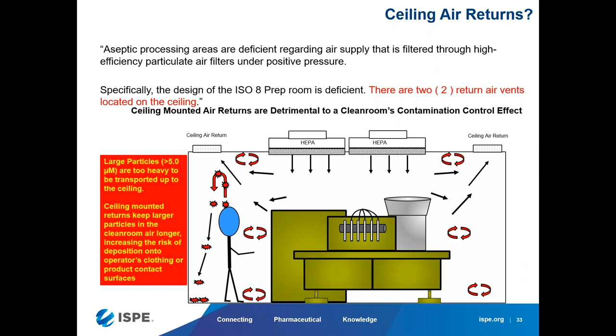Great example is a facility that my team audited. Luckily the client caught it and said, we think there's something off here. They wanted a sterile sampling booth in an ISO 8 room. But the ISO 8 room had ceiling returns, and the sterile sampling booth had negative pressure. That means anything from outside can go inside the sterile sampling booth. Ceiling returns, all 5-micron particles at work level, and the negatively pressured booth sucks them in there. They could have never made any sterile transfer or sterile sampling at all. Very important to understand. This is a very good example, okay?